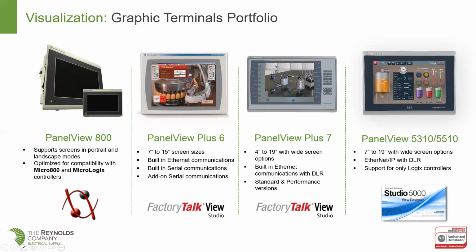It's not an additional cost to add it. It's just part of it, and when you installed it, it was there all along. So that is one of the nice features of the 5000, that you have one software tool for both your Logix and your PanelView. But there are trade-offs in that it only speaks with Logix controllers. Yeah, your third-party devices will have to go through the ControlLogix so we can display information from those products on that HMI.